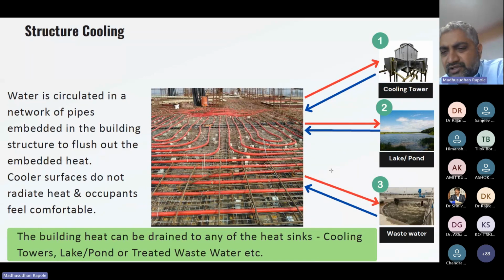So we were already doing something called radiant cooling, but we adapted that because in all radiant cooling installations, we do use a chiller. We were looking at something where we don't have to use a chiller. Even a best water cooled chiller will use around 0.5, 0.6 kilowatt per ton, plus all the pump, cooling tower fan motor energy, condenser pump energy. If you add all that, that is a good 0.7, 0.8, 1 kilowatt per ton at best. But when you use a cooling tower or sometimes even a water body, all I'm looking at is the heat sink. We embed a network of pipes in the building concrete. It could be either in the slab or in the screed, and you regularly circulate water in it to flush out the heat and not allow the heat to accumulate and build. For this, you don't need chilled water, you just need water at 24, 25, 26 degrees centigrade.